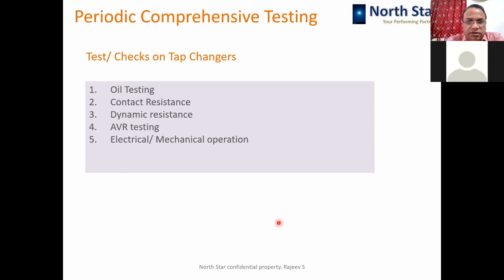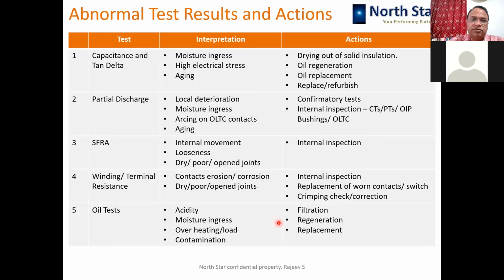Then contact resistance, dynamic resistance, AVR testing, and electrical mechanical operation. So when you invite OLTC maintenance people, they will do all these tests, and it is advisable that only the experts should be called to do these tests. The AVR testing can be done by your own people, as well as electrical mechanical operation can be done. So OLTC is another thing which is to be maintained and tested as a comprehensive testing program of your transformer.